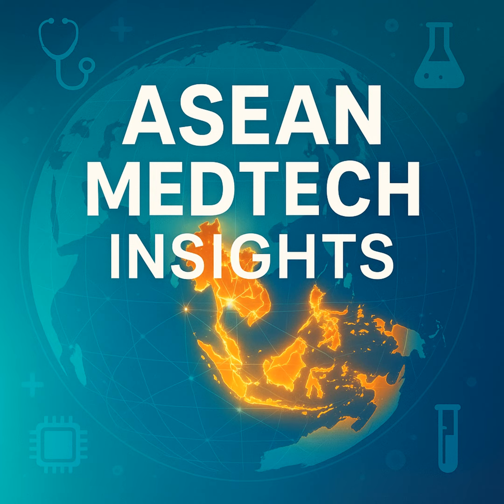First, your SaMD must be classified according to risk. The Philippine FDA uses a four-tiered system, from Class A for low-risk devices to Class D for high-risk ones. For example, a simple diagnostic app that calculates a patient's BMI might be Class A. However, an AI-powered software that analyzes medical images to detect cancer would likely fall into Class C or D. This classification determines the entire regulatory pathway, including the required documentation and the level of scrutiny from the authorities.